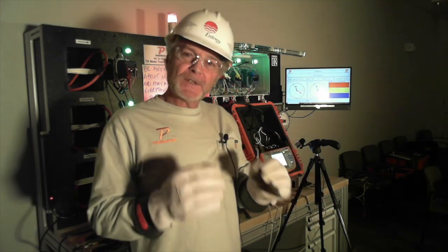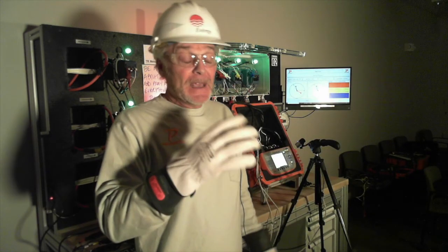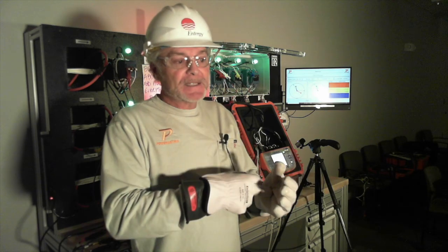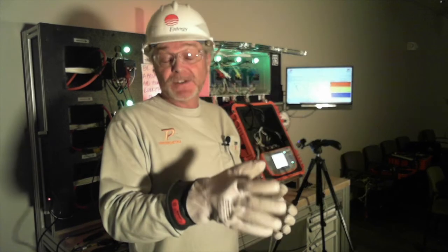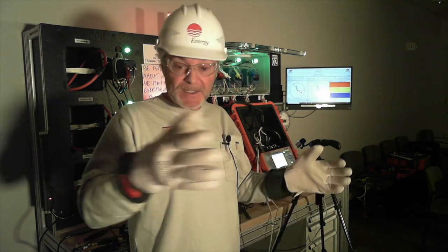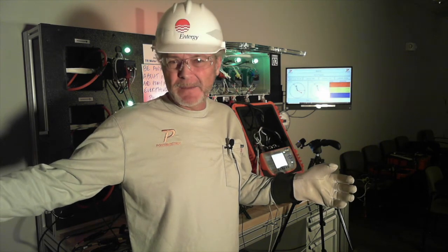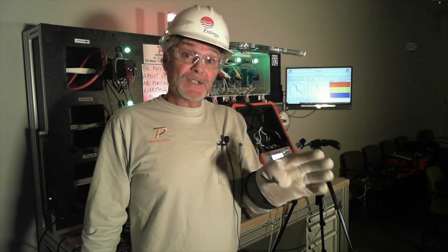So is that really telling you anything? Or would I be more concerned with what I'm losing every single day? Now, if I added 0.1 or 0.3 ohms, then yes, I could say that CT is right on the ragged edge, and you might want to get up there and check the connections to that CT. But if I start adding a whole lot of burden to that CT, what is it really telling me? But if I know what it is, it's the old saying, I can't manage it if I can't measure it.